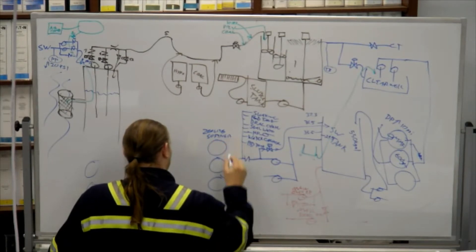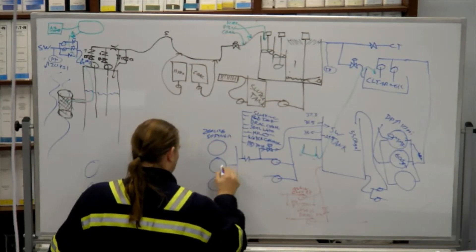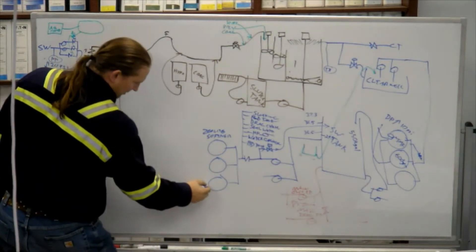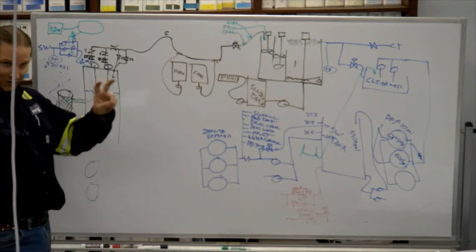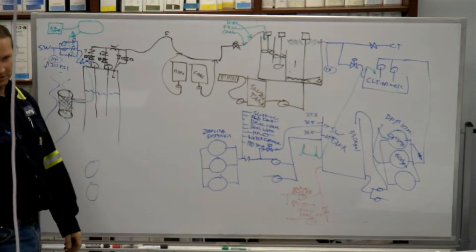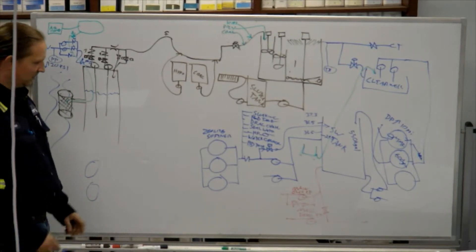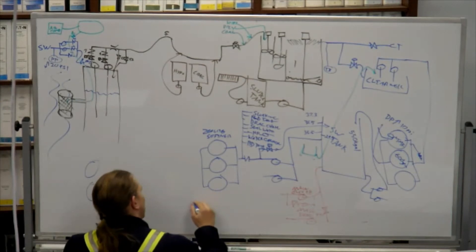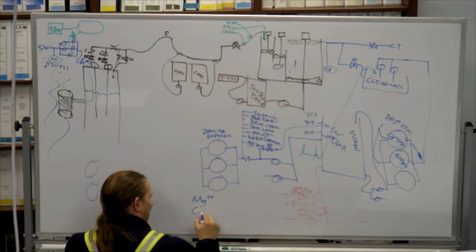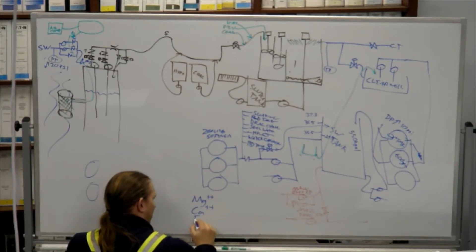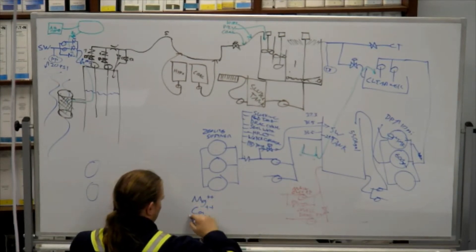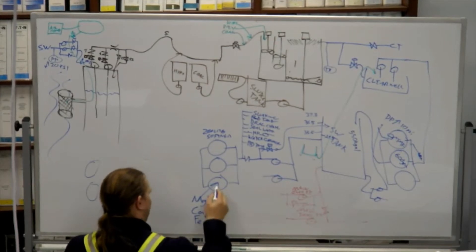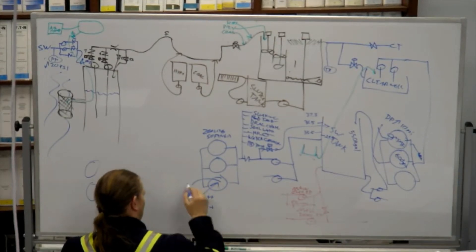What does a softener do? Takes the metals out of the water? Yes. So it removes the hardness, and the hardness is dissolved metals. So we've got things like magnesium, and calcium, and iron ions. And we're taking those out. And we are replacing them with sodium.